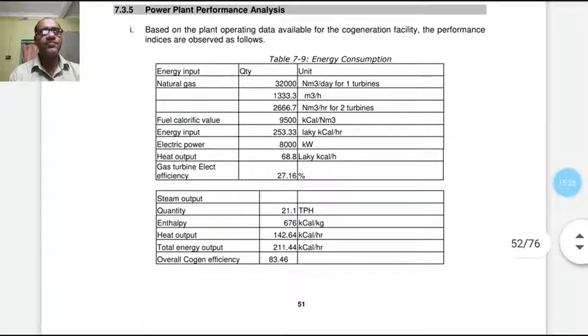Based on power plant operating data available for the cogeneration facility, the performance indicators are observed. That is natural gas quantity, 32,000 Nm³ per day for one turbine. That is 1333.3 Nm³ per hour, and 2666.7 Nm³ per hour for two turbines. Calorific value 9500 kilocalorie per meter cube. Energy input 253.33 lakh kilocalorie per hour. Electric power 8000 kilowatt. Heat output 68.8 lakh kilocalorie per hour.